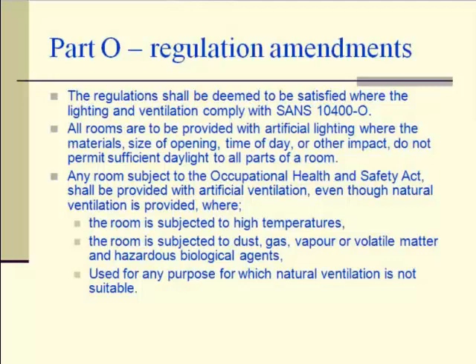In terms of design requirements, occupation health and safety has different criteria to the minimum standards, and there are green building guidelines where you try to minimise the amount of lighting and rely on task lighting or other systems. Whatever you do, if you stipulate a 400 lux level, that design lux has to be there and achievable all the time — it doesn't start at 400 and depreciate to around 350 over time due to globe degradation. It has to be a minimum of 400 for the entire time that light is required. We need to make sure when working with consultants that we achieve this, because a lot of places currently don't comply.